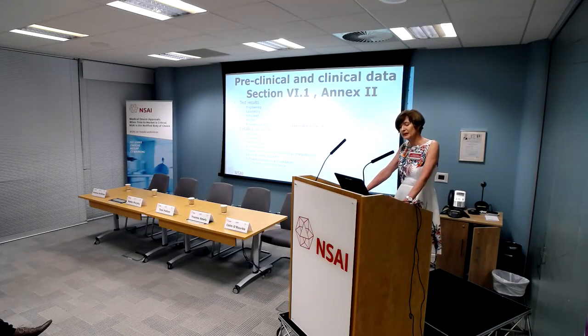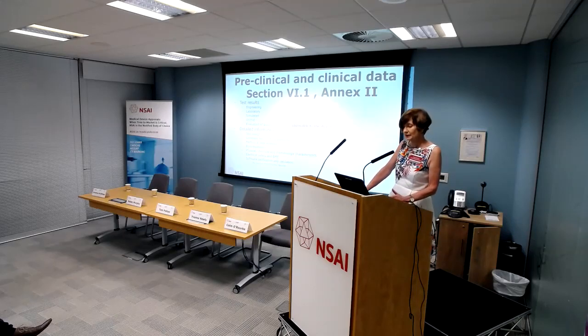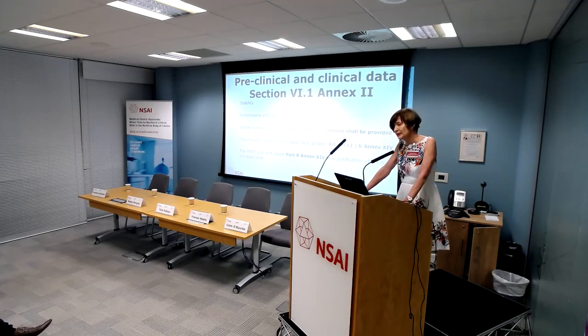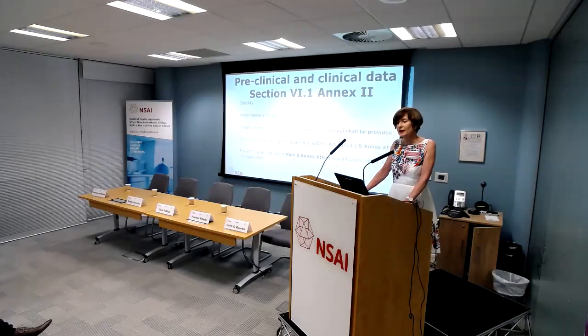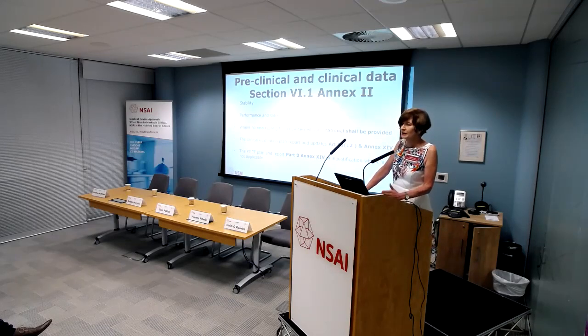We will look for detailed information on how you do your test design, your test studies, or your protocols, your methods of data analysis, again, the biocompatibility that Colin referred to, the physical, chemical, and microbiological characteristics, electrical safety, software. Depending on what the type of product you have, different requirements will be applicable. The stability, and we're not only looking at stability of the product, we also need to look at the stability of the packaging. People tend to give you one and not the other. The two have to go hand in hand, particularly if it's a sterile device, that packaging has to remain stable until the end of shelf life.